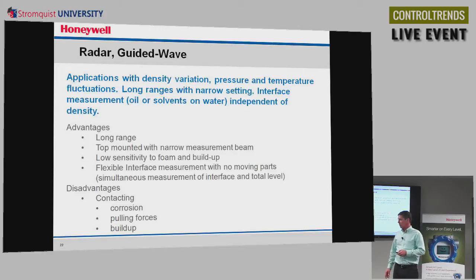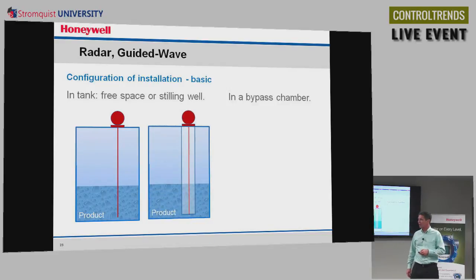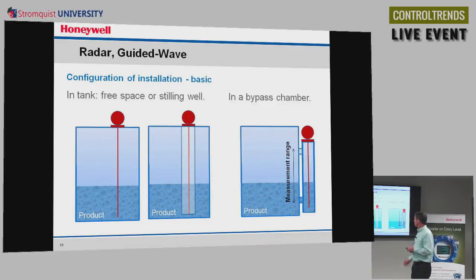The disadvantage is this does come in contact with the process. There can be issues with pulling forces, with corrosion, and buildup. The mounting can be just simple, like we're showing here on the left. It can be with the stilling well to sort of calm the surface and focus the wave. And then we talked about a bypass too. This gives us isolation from the process, and gives a nice calm surface too.